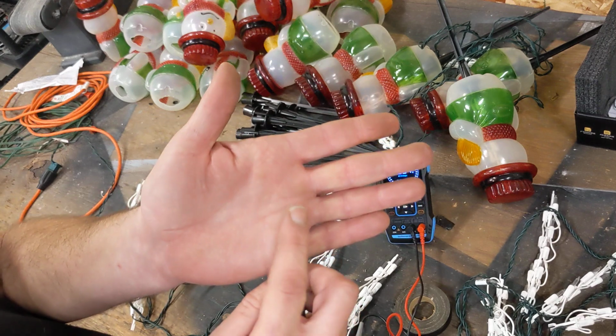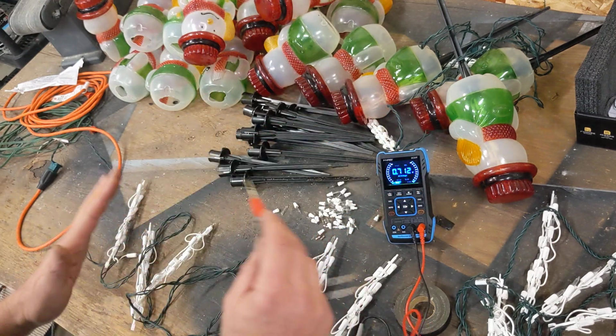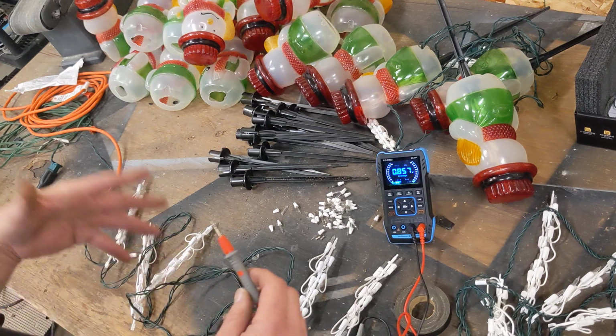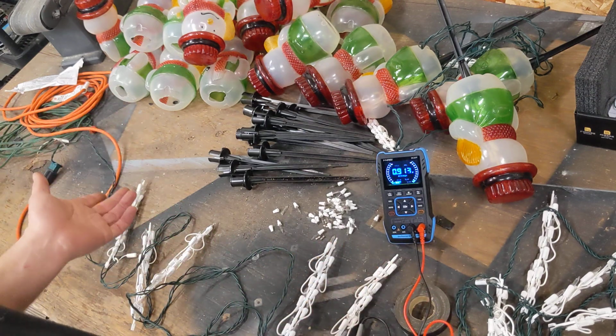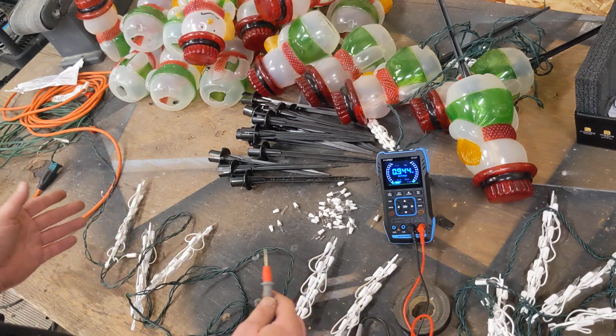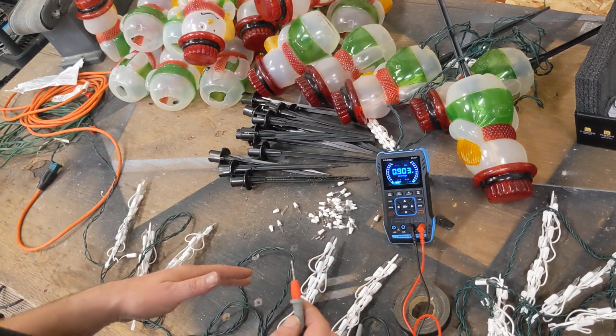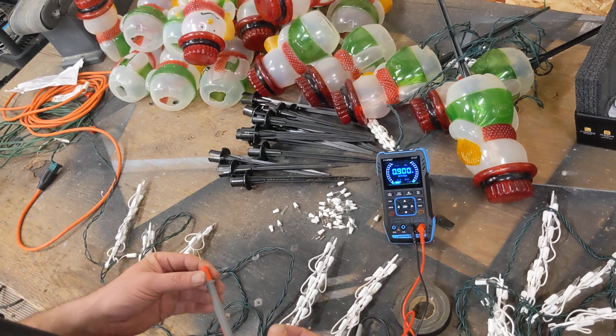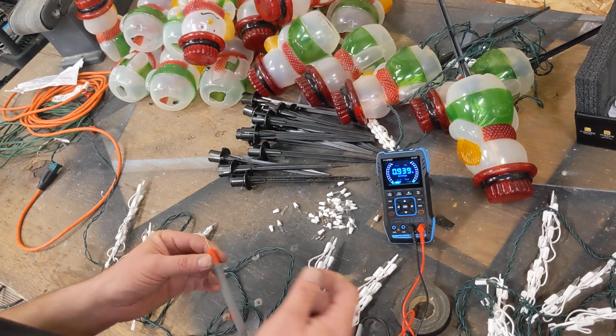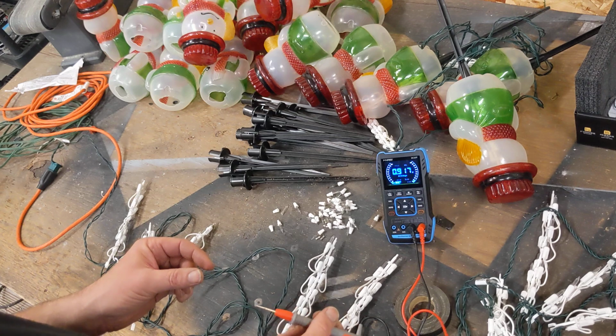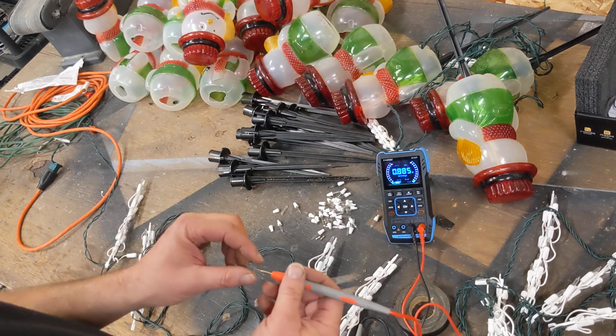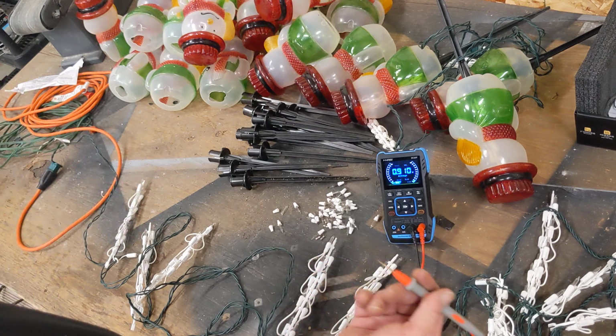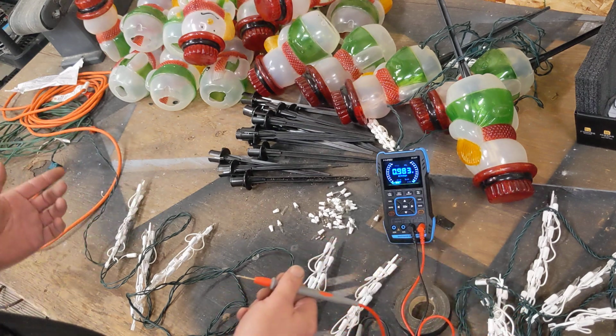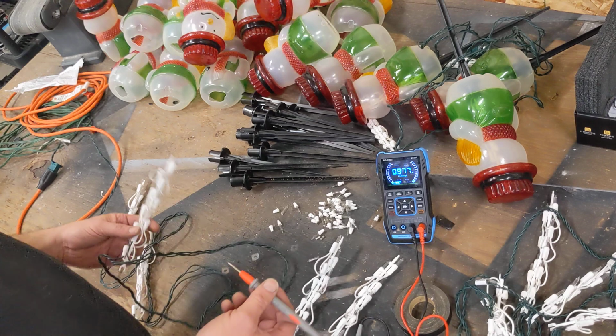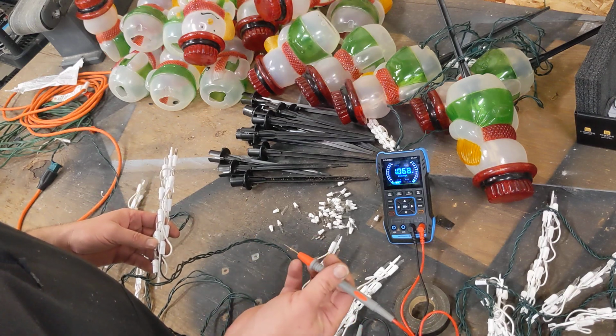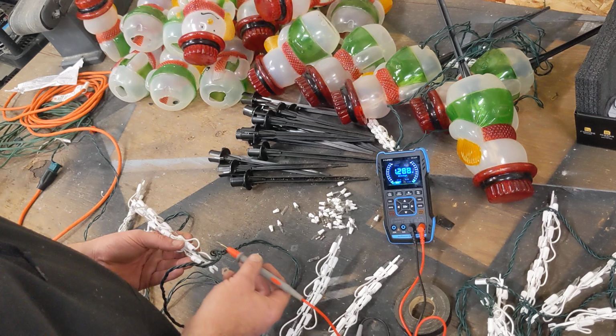If you have a needle point on your probe, it makes it very easy to check these things. A lot of the cheaper probes, if you go down to Harbor Freight and buy their $5 or $7 multimeter, it's going to have some pretty thick probes, and you won't be able to back probe like that. A couple things you can do: shove a sewing needle up in there and clamp it, or just touch your probe to the sewing needle. Or they sell back probe kits right next to the multimeters at Harbor Freight for about $4 or $5. It's basically just an extension for your probe that you slide up in there, and then you touch your probe to that.